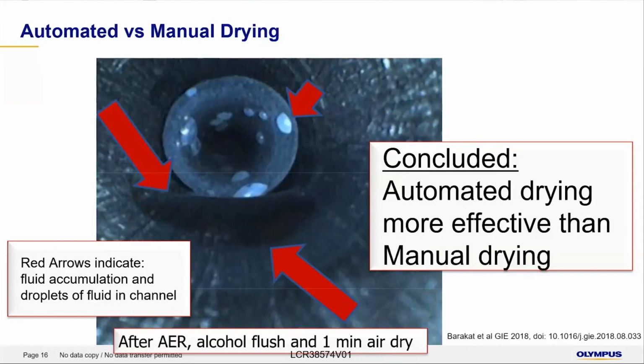I won't bore you with the details, but basically Barakat did a number of assessments to determine the best way to get these scope channels dry. What they recommended was automated drying, where an air flushing pump could be used, and it was more effective than having a staff person standing there with a compressed air gun drying each of the channels for 10 minutes. So again, automation facilitates improving the quality process. The other thing is that there are channel purge storage cabinets, storage cabinets that will flush air through the channel, so that you can engineer safety into this process. But I think the awareness came with the borescope studies that were done by Ofstead and also by Barakat.